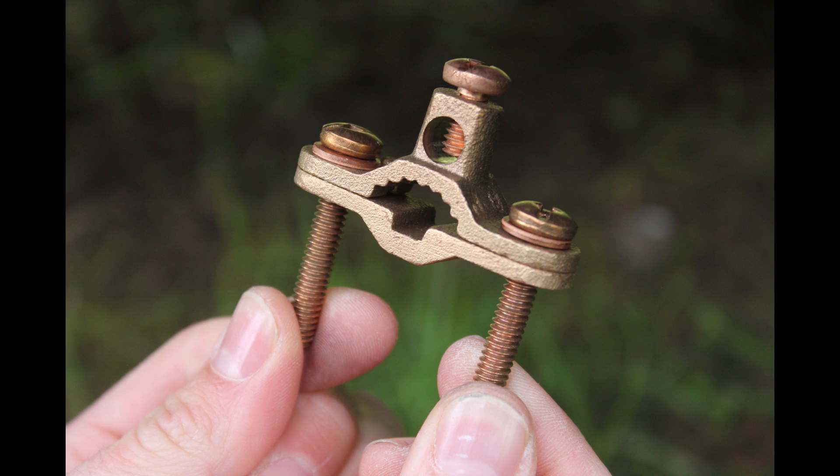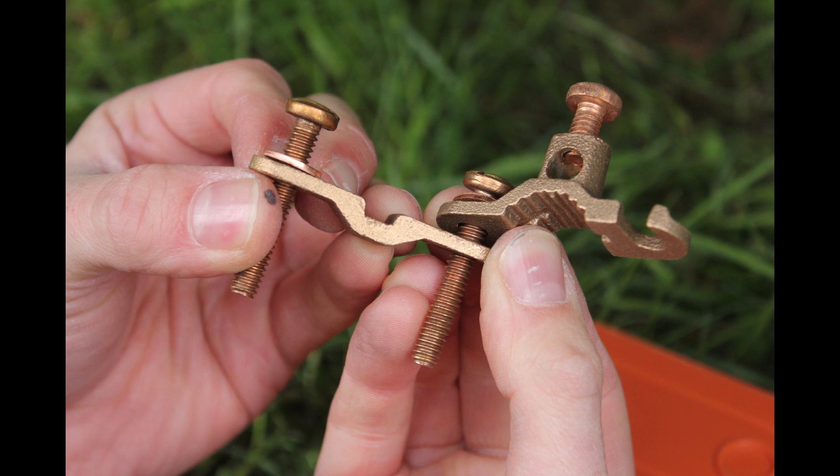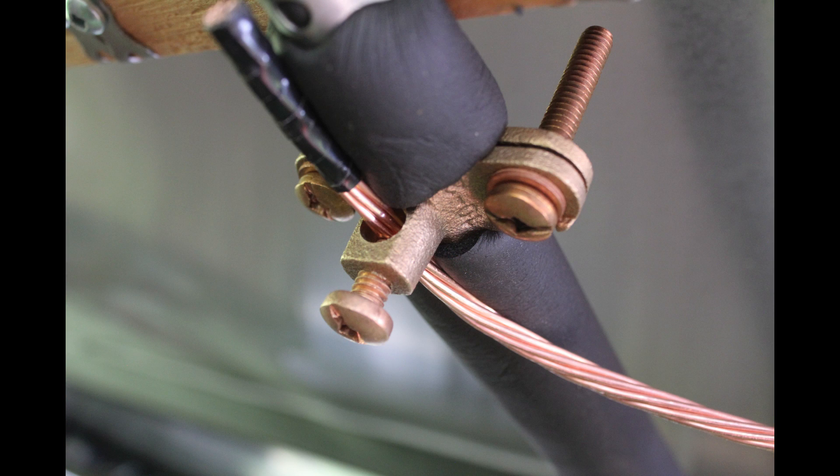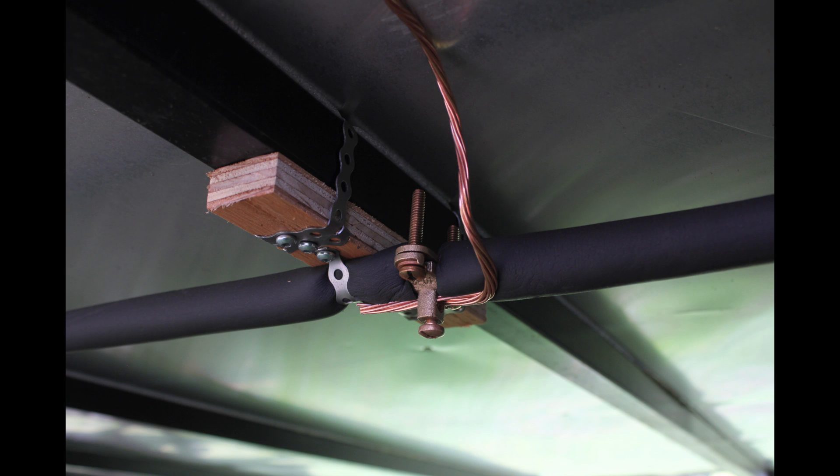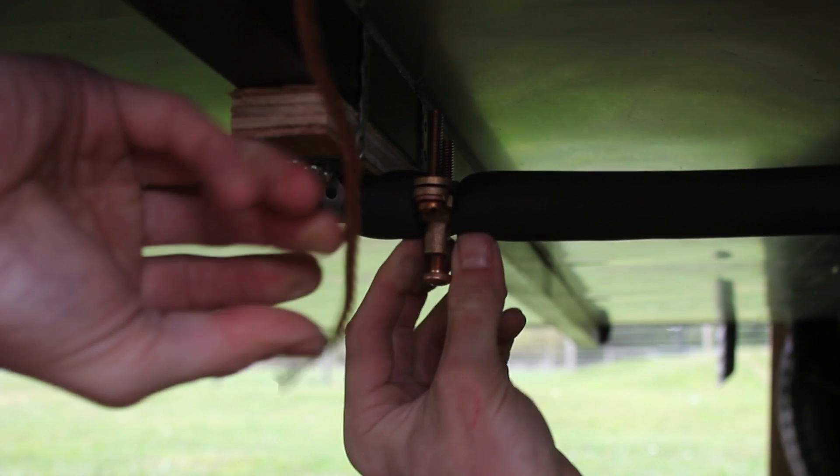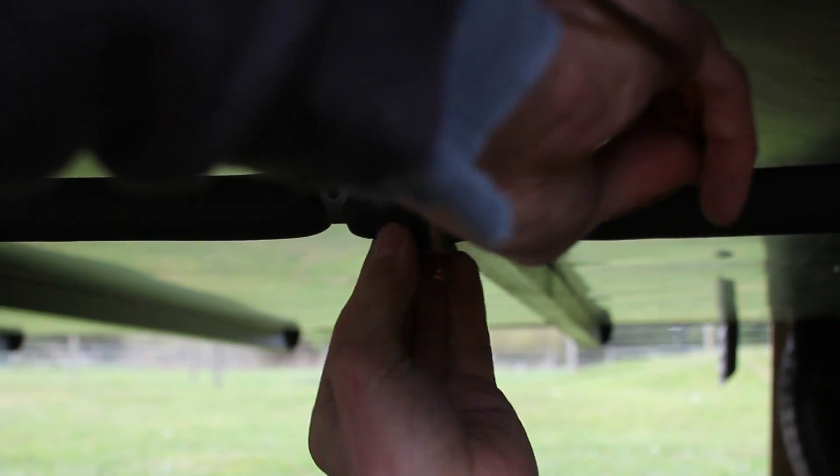And then this is a pipe bonding clamp and it's great because it can swing open and then can just be fit around an existing pipe and then it will cinch down. Obviously you don't want to crush the pipe but we'll get it so it's just snug and making a good electrical bite onto the pipe and then the top hole is a provision to allow the bonding conductor to go through.